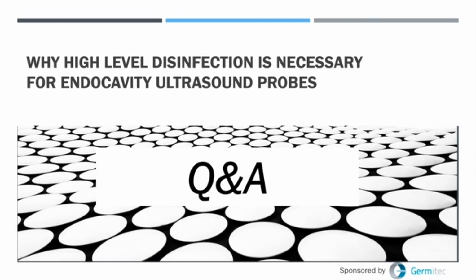My manager recently implemented a new automated disinfection system, not just because it was quicker, but because it was rigorously tested against HPV. What evidence do you need to prove a system has been tested against HPV? That is really an excellent question. So there are several ways to test against HPV. HPV is very difficult to culture. So the most common way of testing is to actually look for HPV DNA, which can be done. And certainly if there's no DNA on the device after cleaning and disinfection, then you have eliminated all the HPV.